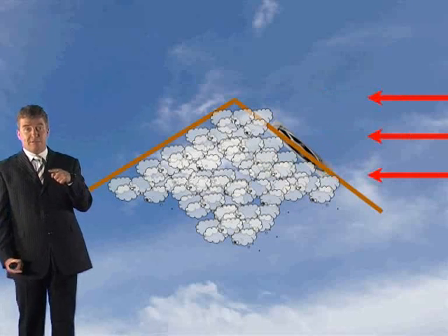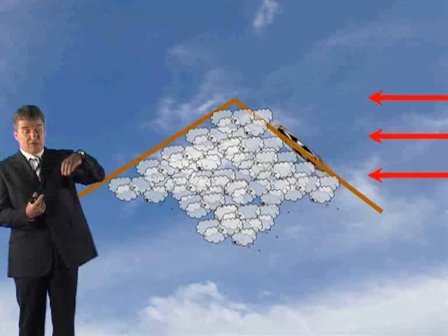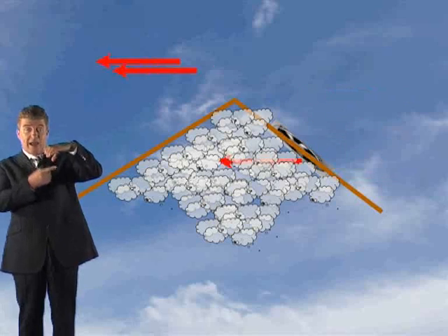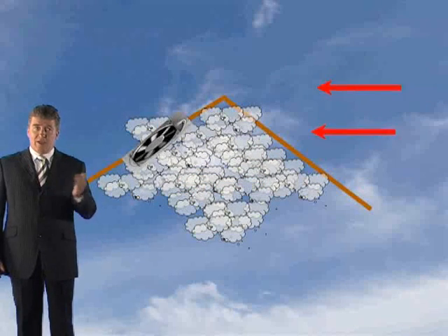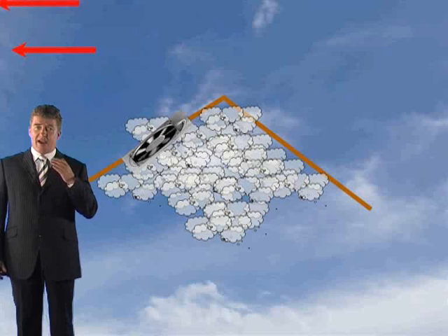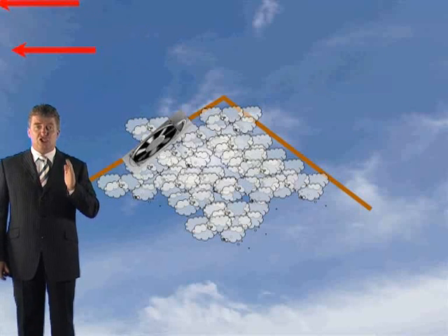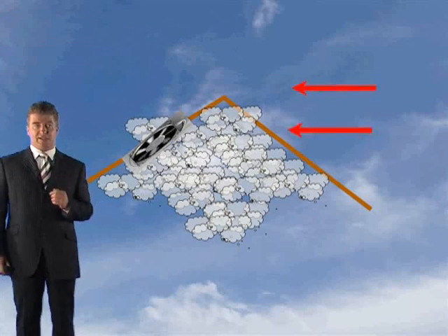In other words, if the force pushing it out is less than the positive pressure above it, the wind for example, it's not going to push it out, it's going to push it in. However, if the ventilator is sited in an area of negative wind pressure, then the resultant suction force will actually improve the system. So if you've got smoke coming out and you've got negative pressure above it, it will speed up the process and increase the rate of exhaust.